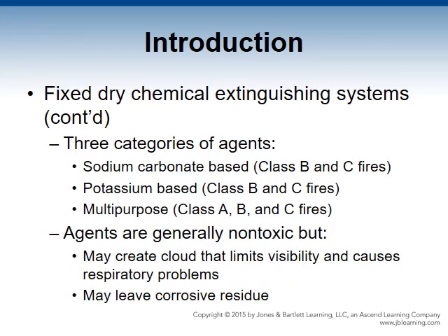The categories of these agents. You have three. You have sodium bicarbonate base, which works well on Class B and C fires. One of the oldest and most widely used dry chemical agents on cooking-related grease fires. It can be white or blue in color.